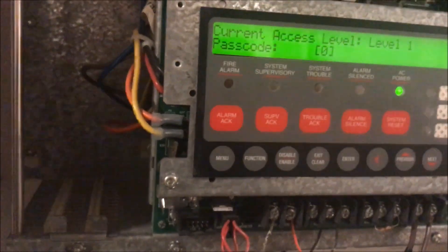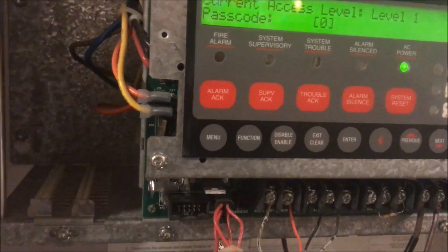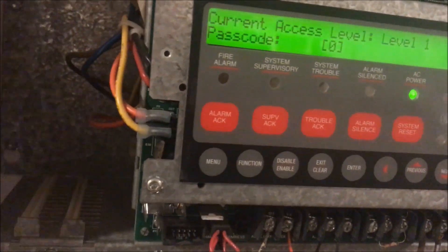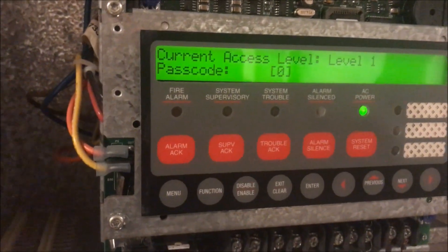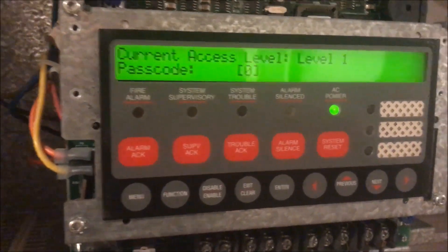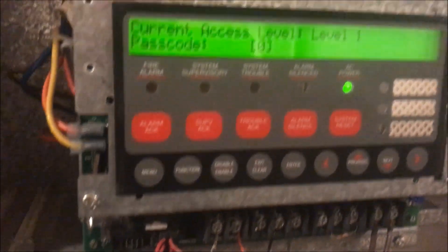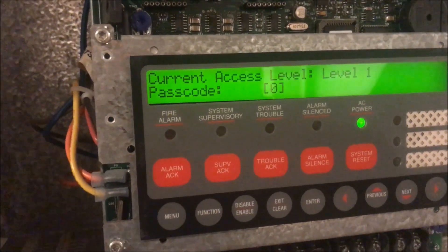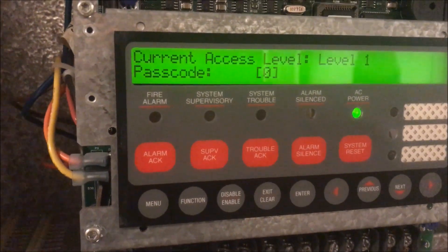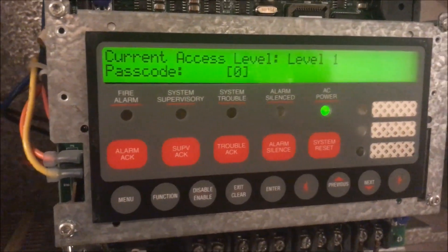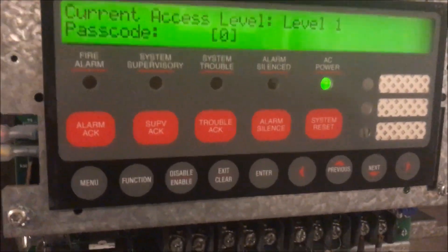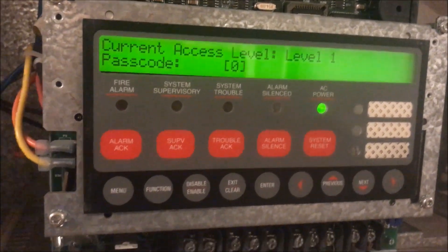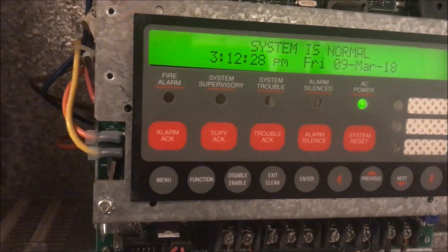Level one is the most basic level. Level two gives you a little bit more access and requires a login — everything after level one requires a login. Level three gives you a moderate amount of access but not everything. Level four, when you log in, actually puts the panel into trouble because it enters service mode — that's where you're adding points, deleting points, reconfiguring points, doing a factory reset — massive changes to the panel.